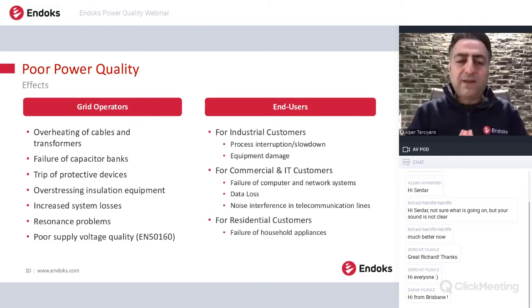Overvoltage is very, very important since distributed energy resources are becoming more and more present in the distribution system. Then the overvoltage problems are becoming more important and critical for the grid operators. Because of these overvoltages, there are many problems on the insulation equipment. And of course, the increased losses and the resonance problems are very important because of harmonics.